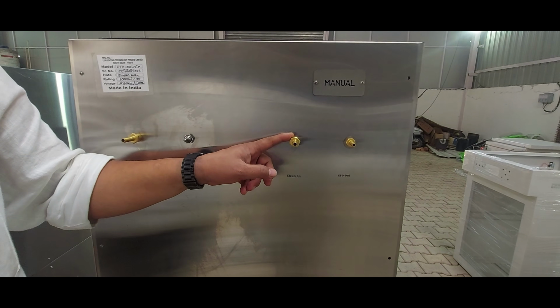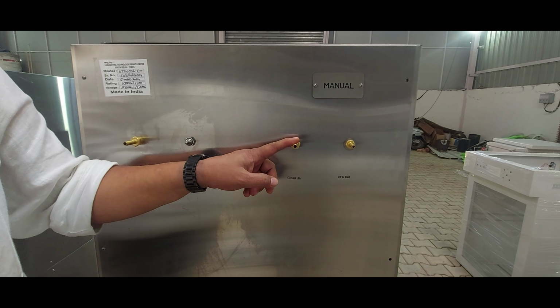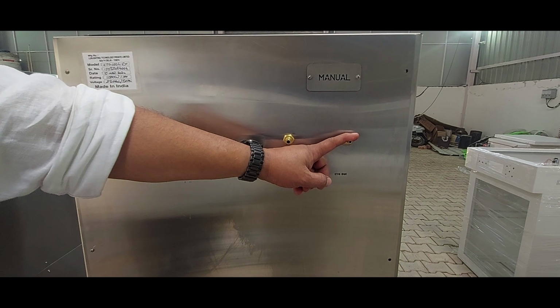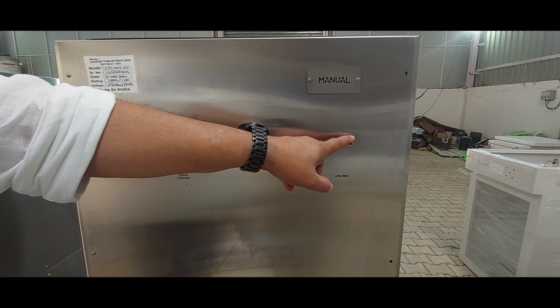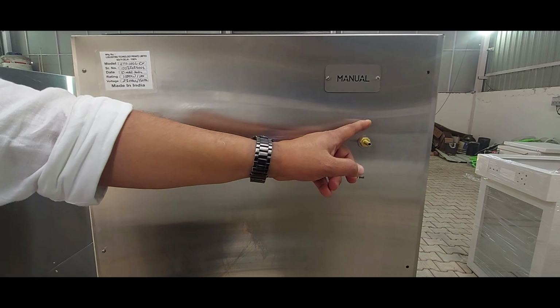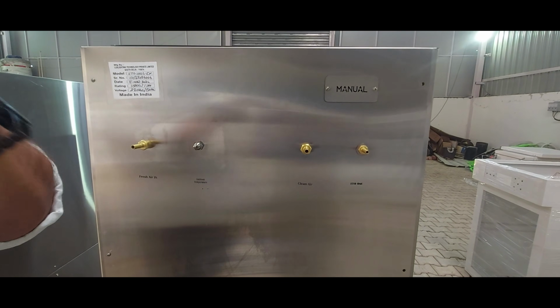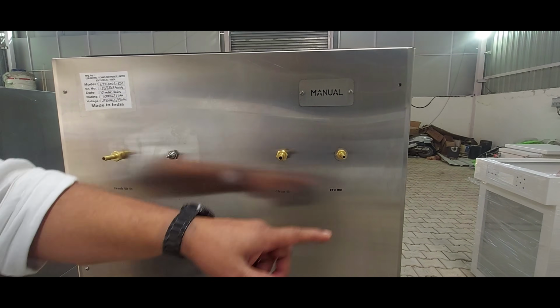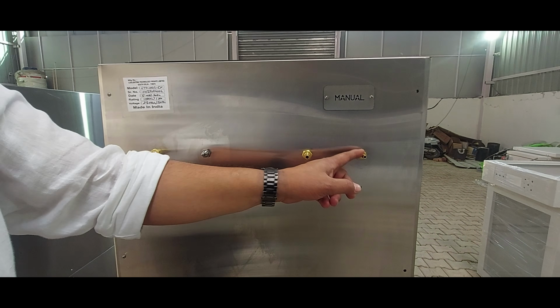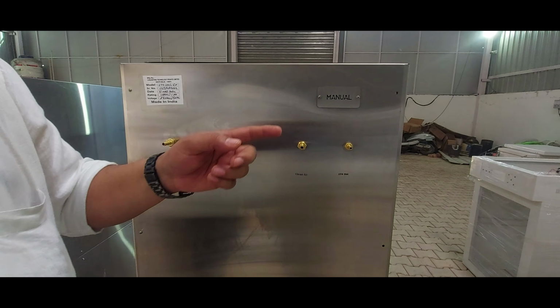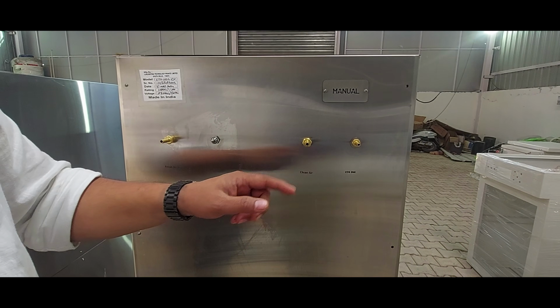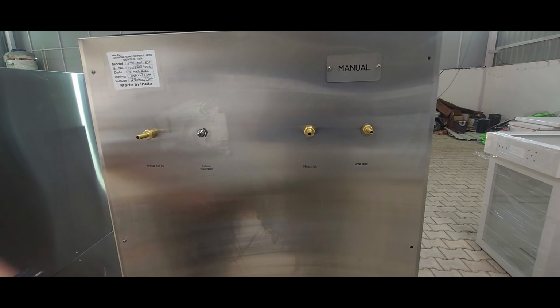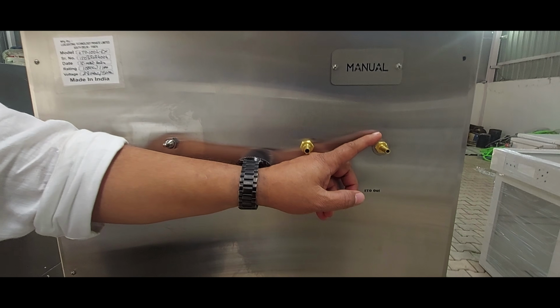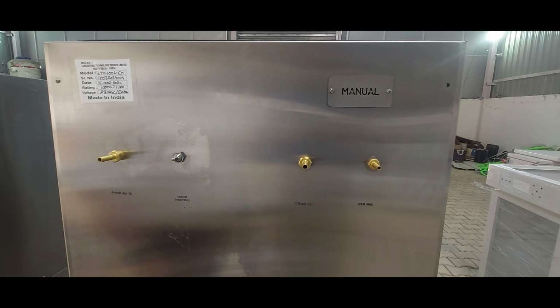1. Preconditioning. This stage prepares the chamber for sterilization by removing air, performing a leak test, and conditioning the environment with steam or humidity. This can involve a series of partial vacuums followed by nitrogen injections to purge the air. 2. Gas introduction. Optional on-process requirement, on-demand design, ETO gas is introduced into the chamber. The gas is often mixed with other substances like CO2 or steam to reduce the concentration of ETO and improve safety.